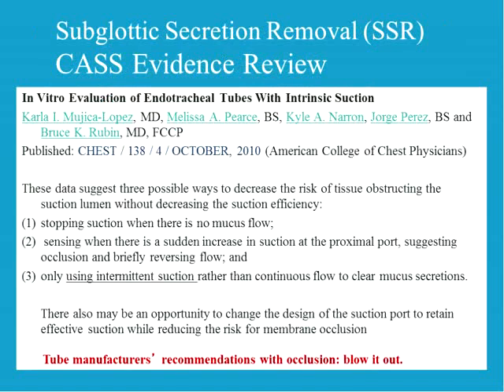Some say use less than 150, which is the AARC clinical practice guideline for endotracheal suctioning. What Bruce Rubin's lab showed is that anytime you use more than 120 millimeters of mercury, you're going to occlude the tube every time. So again, with all suction, use the minimal amount to achieve the goal. If you're moving good secretions at 80 millimeters of mercury or at 50 millimeters of mercury, then that's the amount of pressure that you should use. There also may be an opportunity to change the design of the suction port to retain effective suction, and that actually has been done by specifically the Mallinckrodt people.